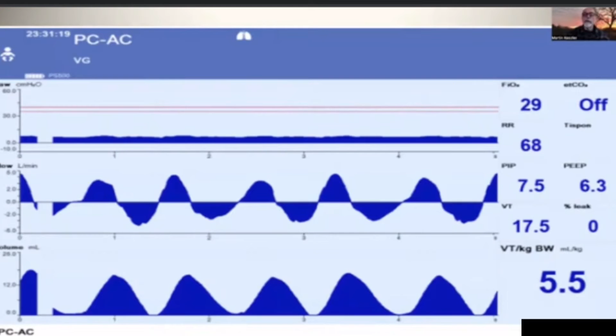Let's briefly talk about leak compensation, because leak around the endotracheal tube is another concern why some people are hesitant to use volume targeted ventilation in neonates. But the Draeger ventilator, the VN500 and the more recent 600 and 800 iterations have a very effective leak compensation algorithm. I won't go into the details, but for example here, if we have a 6 ml tidal volume going in and there is a large enough leak, most of the leak is during the inspiratory phase. So let's say 2 ml or a third of the tidal volume disappears due to leak around the endotracheal tube, and only 4 ml enters the patient's lungs.